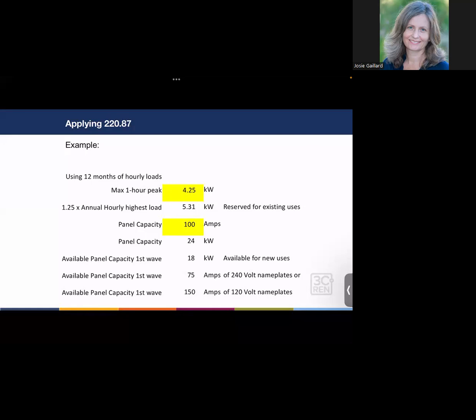So if we know we have 24 kilowatts available, historically we've been using at our peak 4.25, which gets bumped up to 5.3 just as a sort of safety factor. So that means we have even over 18 kilowatts available for new uses. Changing that into amps, we have 75 amps. So really 3/4 of this 100 amp panel is available for new uses. And that's 240 volt, so big appliances with those chunky dryer plugs, or big heavy duty appliances.